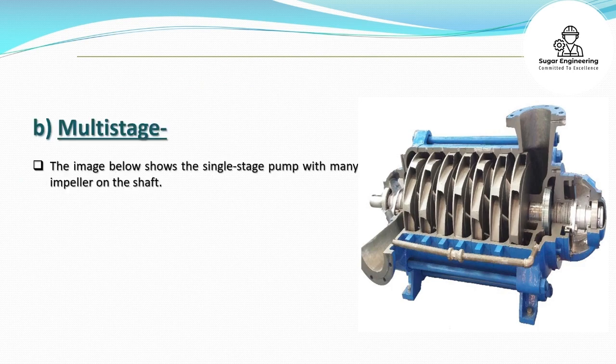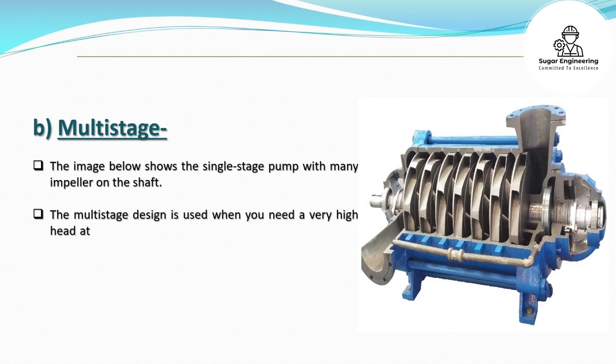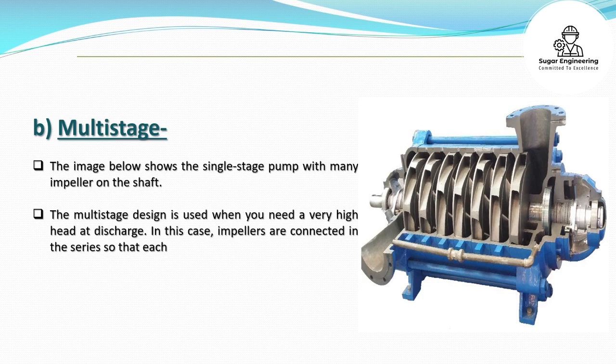B. Multistage — this shows a single stage pump with many impellers on the shaft. The multistage design is used when you need a very high head at discharge. In this case, impellers are connected in series so that each stage will boost the fluid pressure.